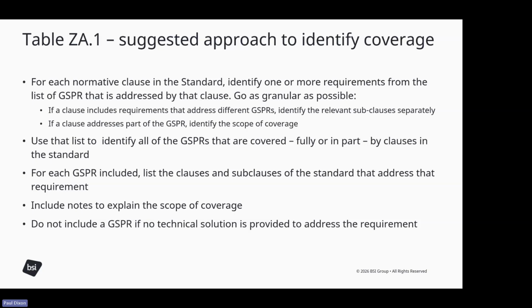My recommendation is that you start out by going through the standard and for each clause, identify where in the GSPR that clause would fit and go as granular as possible. If you start out with the GSPRs, it's a much more burdensome process because you'll be reading a lot of GSPRs that are not relevant to your product. If you start with the clauses of the standard, tie them to the GSPRs and then use that to fill in the table, essentially by reversing the traceability, that seems to work better. So you're going to use your list to identify all of the GSPRs that you think are covered, either fully or in part by clauses of your standard. And then you're going to list those in the table and include notes.